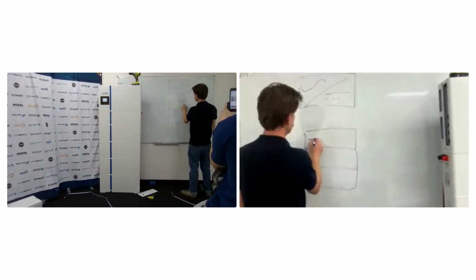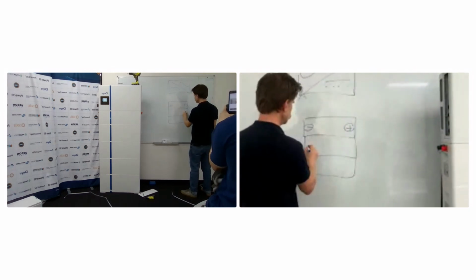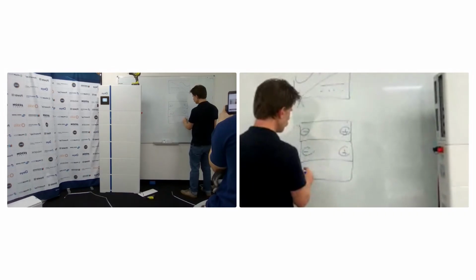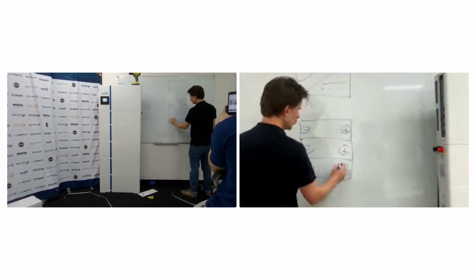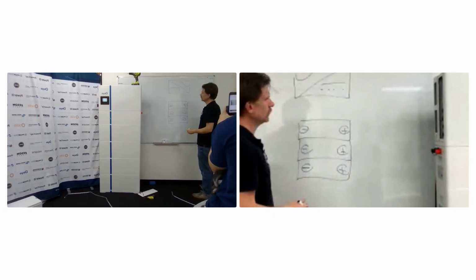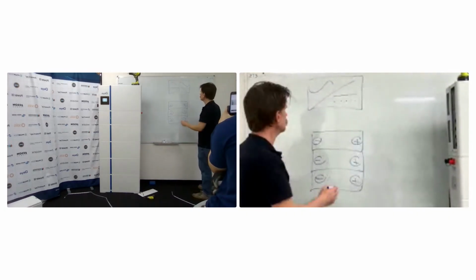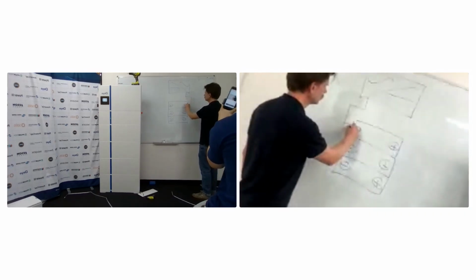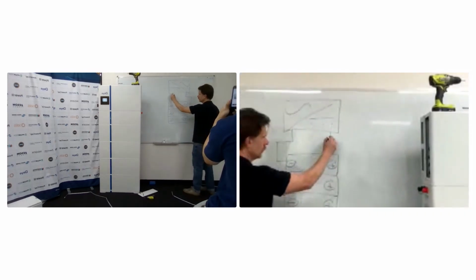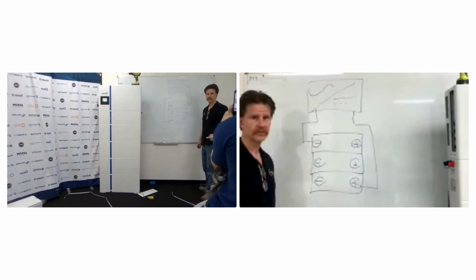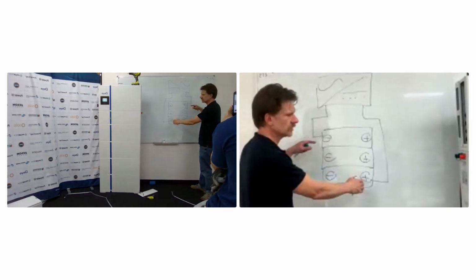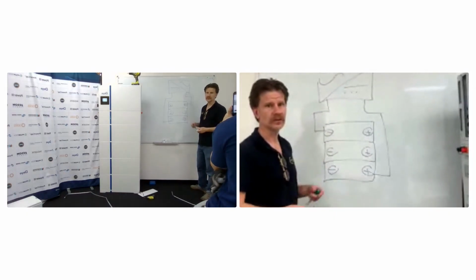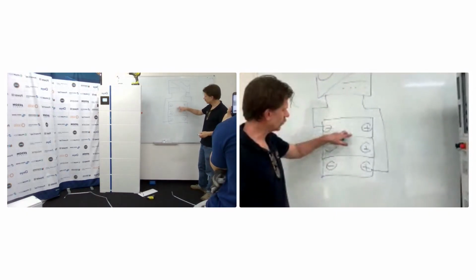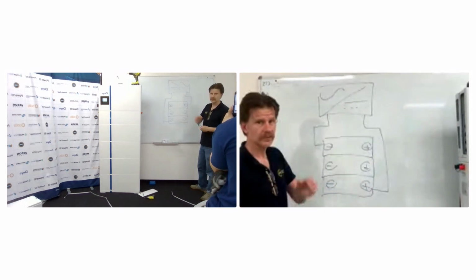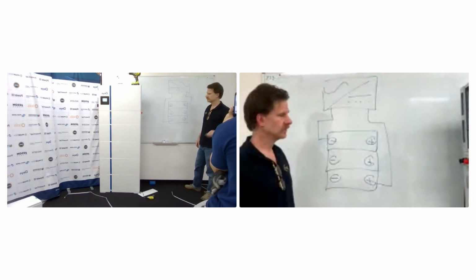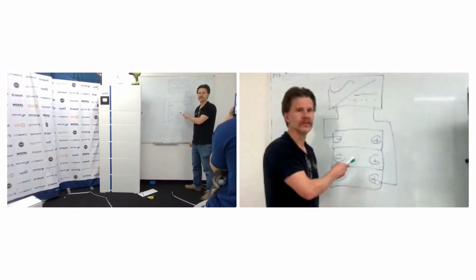We've got positive and negative on each battery, and they're wired in parallel, not in series. If you were doing this strictly speaking, the way you'd want to wire it is your negative connects to the top one, and your positive connects to the bottom one, so that you've got an equal amount of resistance across the entire bank. That way it's not the case that the first battery sees a higher voltage than the last battery. When you're dealing with lead acid battery banks, this is a really big concern.